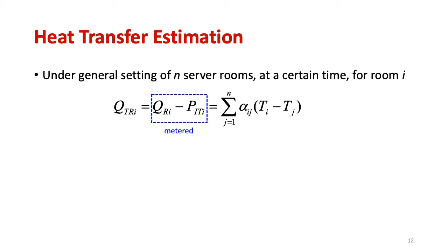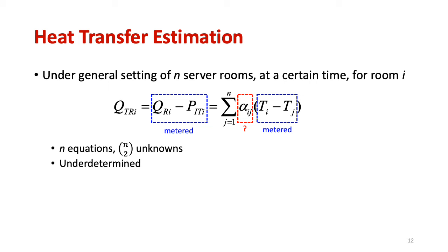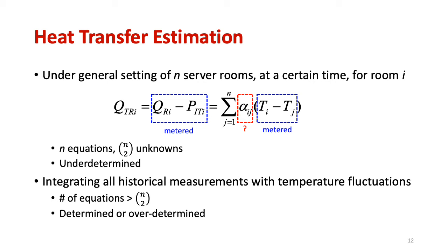In this equation, those two terms are metered. The room temperatures are also metered, so the heat transfer coefficient is to be estimated. Since we have a total of n rooms, we can write down a system of n such equations, but we have n choose 2 heat transfer coefficients to be estimated, so the problem is underdetermined. To address this issue, we integrate all historical measurements with temperature fluctuations, such that the number of equations is greater than n choose 2, and the problem becomes determined or overdetermined. Once we obtain the heat transfer coefficients, we can estimate the heat transfer between any two rooms at any time.